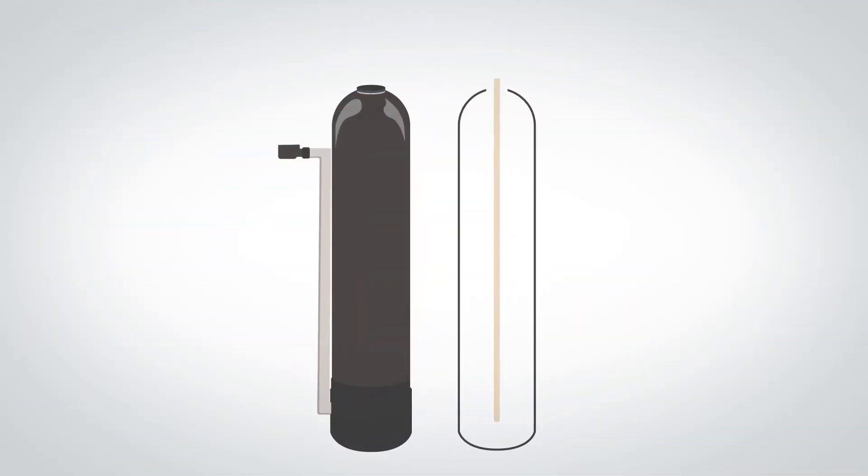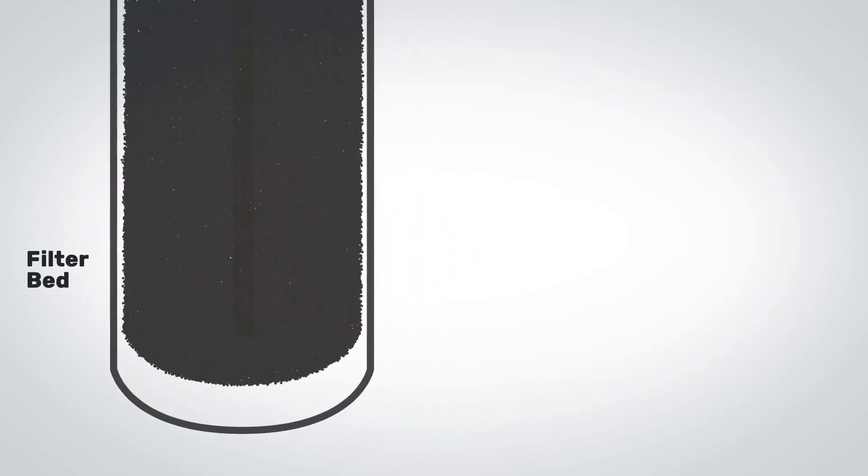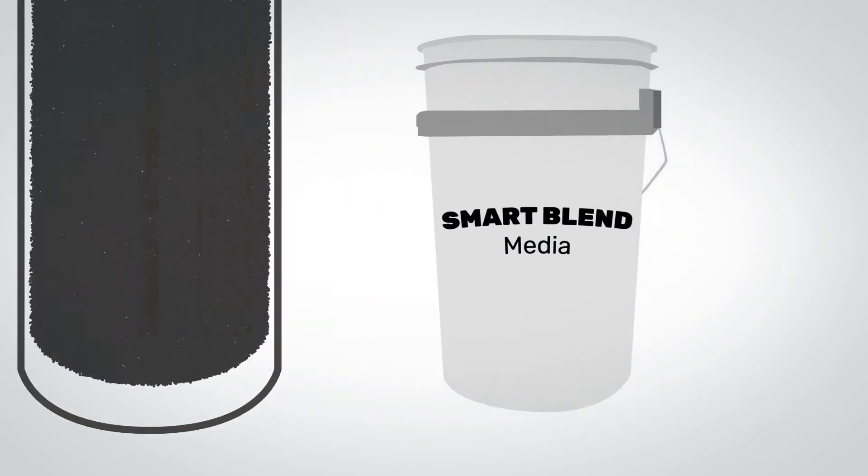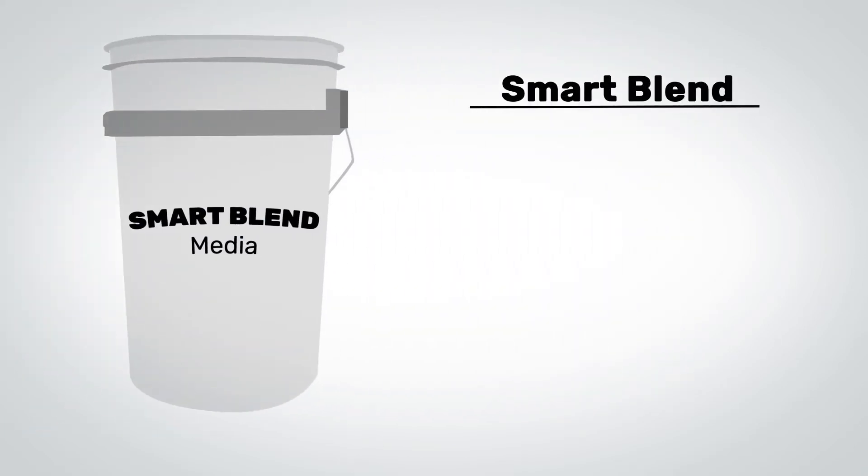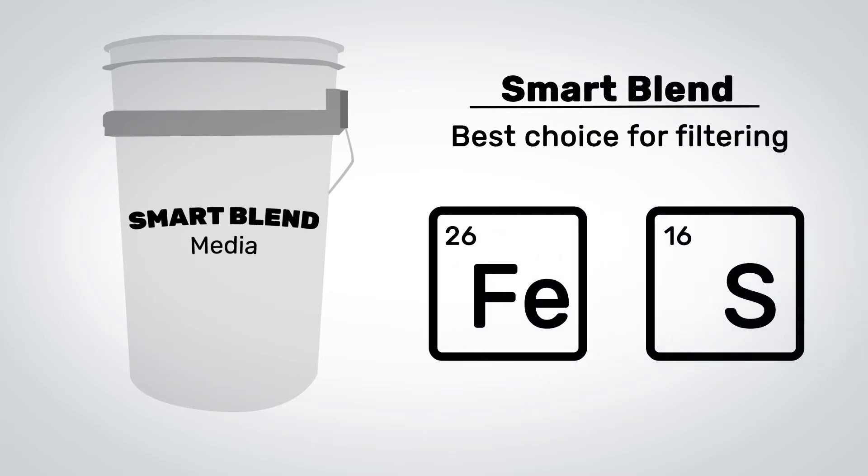Our single tank aeration filter uses a fiberglass tank with a riser tube going up through the middle of the tank and a filter bed located in the lower two-thirds of the tank. The filter bed is made of a granular substance referred to as media. The media typically used in our aeration filter is smart blend, which is the best choice for filtering iron or a combination of iron and sulfur, though other types of media may be used in certain situations depending on your water quality.